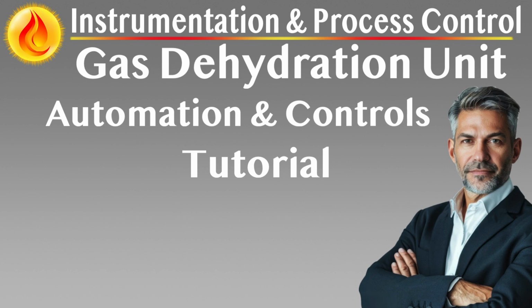Lean glycol flow management. Positive displacement glycol pumps deliver lean glycol to the contactor top. For systems with multiple contactors, flow split is regulated via dedicated flow control valves. In structured packing systems, glycol flow remains fixed to ensure adequate wetting. Flow feedback ensures circulation is matched to required unit circulation rate, UCR. Temperature regulation. Lean glycol temperature is monitored to maintain it above the inlet gas temperature, preventing retrograde condensation and associated foaming. Alarms are triggered if glycol temperature falls below this margin.